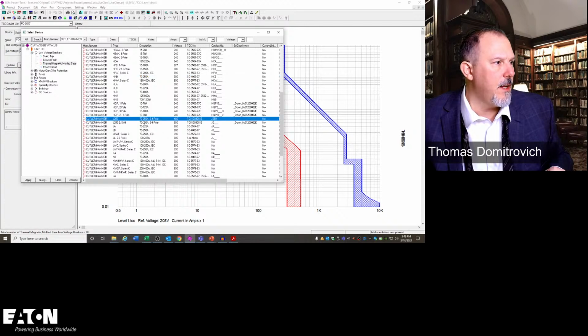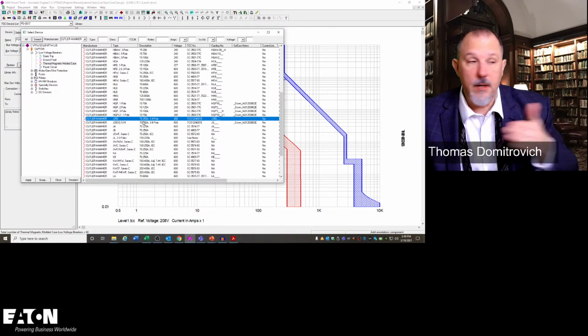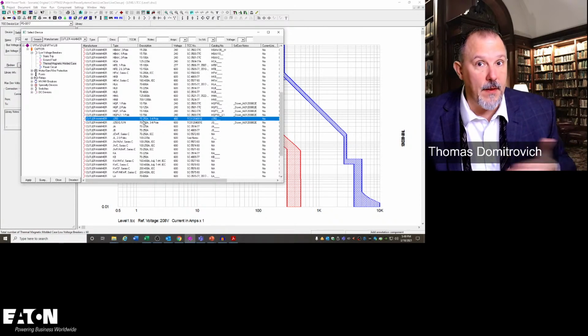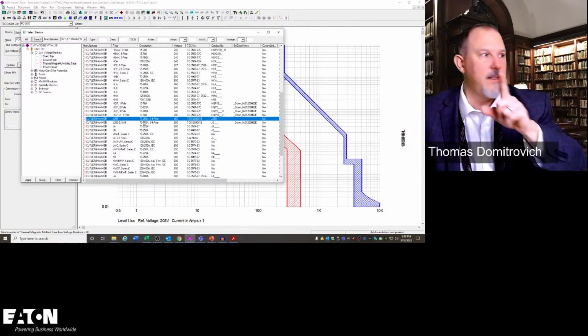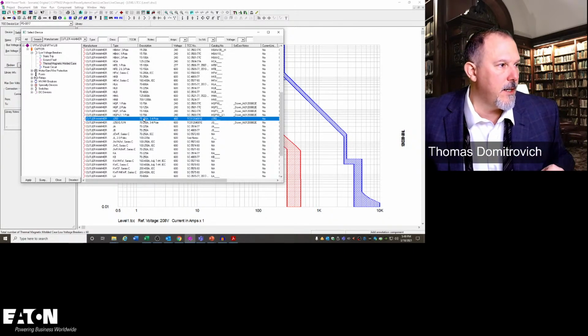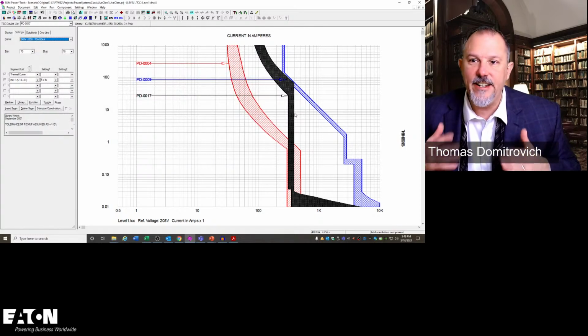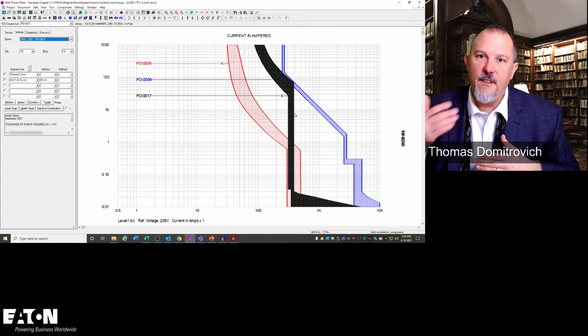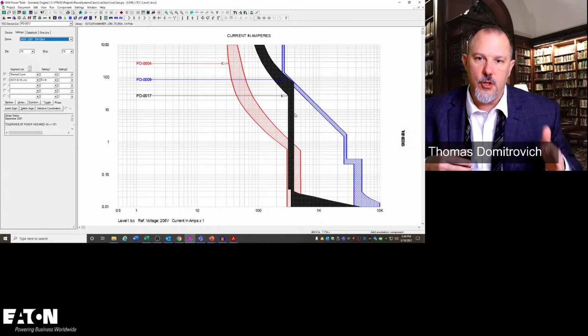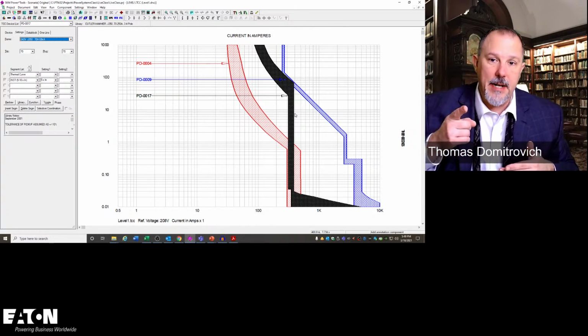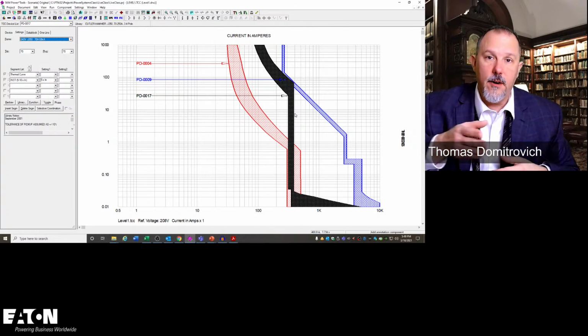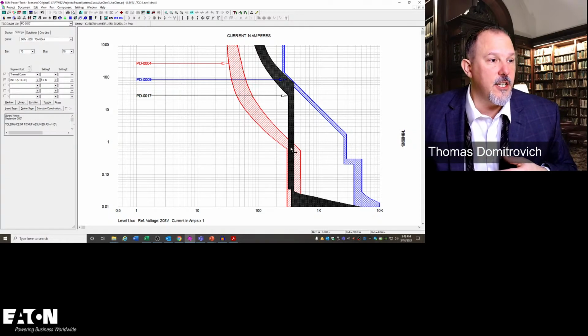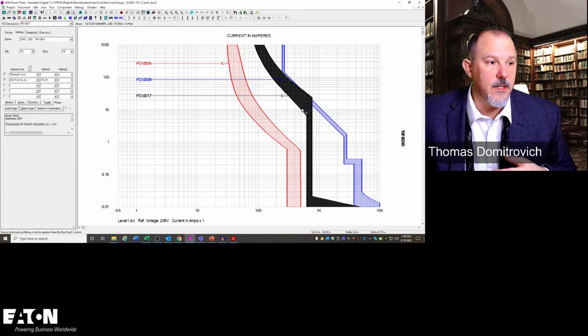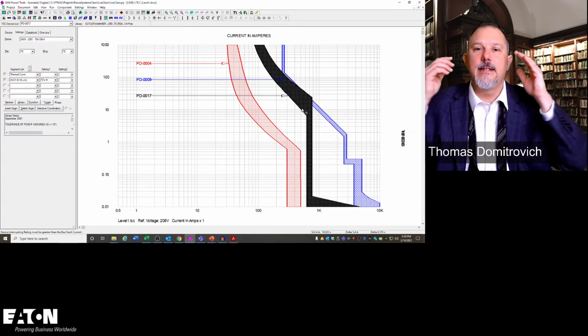There's a 250 J frame. K frames are bigger than J frames, so J frames have got to be cheaper than K frames. So I'm going to double click on that. Now this is a 480 volt breaker. Question, Mr. Ryan Jackson: can I apply a 480 volt rated breaker on a 208 volt system? For anybody out there, can I apply a 480 volt rated breaker on a 208 volt system? And does it change the trip curve? Yay or nay, saith thee.